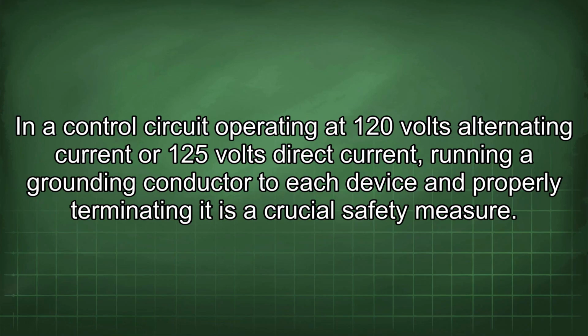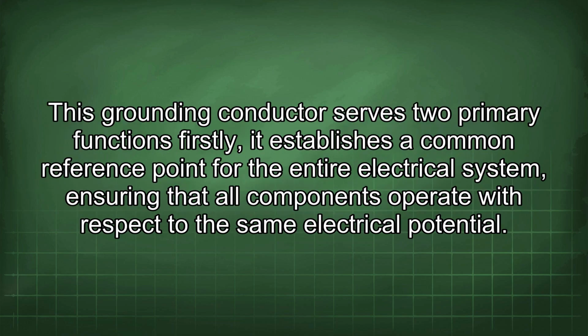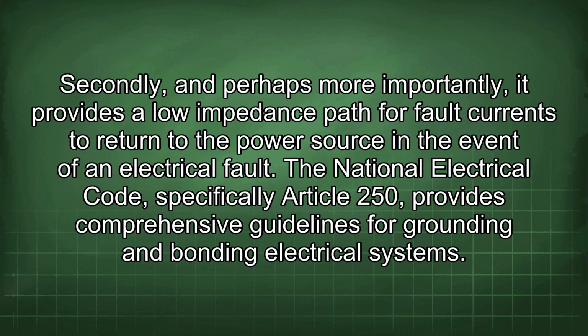In a control circuit operating at 120 volts alternating current or 125 volts direct current, running a grounding conductor to each device and properly terminating it is a crucial safety measure. This grounding conductor serves two primary functions. Firstly, it establishes a common reference point for the entire electrical system, ensuring that all components operate with respect to the same electrical potential. Secondly, and perhaps more importantly, it provides a low impedance path for fault currents to return to the power source in the event of an electrical fault.